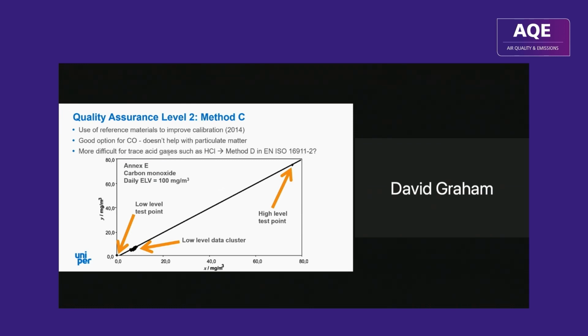And generally speaking, it's much more difficult for low concentrations of acid gases, such as HCl, where you're close to detection limit. And perhaps the use of method D, or procedure D, introduced in the flow standard, would be useful here, and that just involves forcing the calibration function through zero. That should certainly be considered more, but we're having presentations on particulate and HCl later.